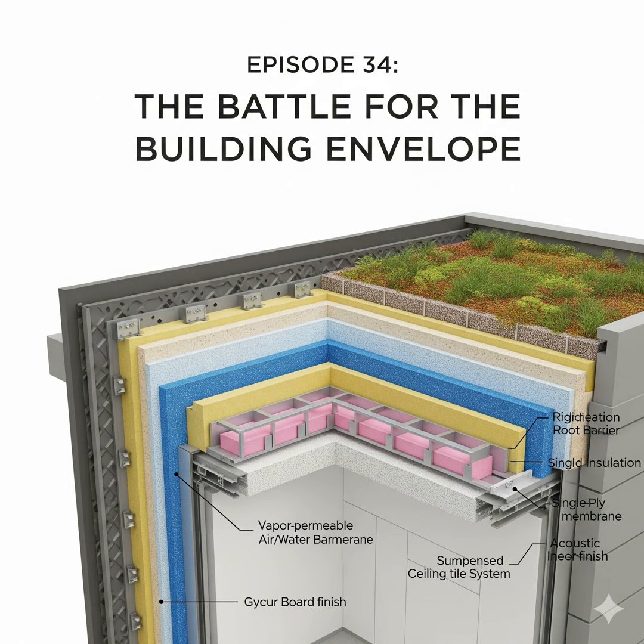And the big metal box connected to it, the supply plenum, notorious for leaking at the seams. The recommendation for those areas, because they vibrate and flex more, is to use both fabric and mastic, like a mesh tape embedded in a goopy sealant. That level of detail shows you how determined air is to find a way through.